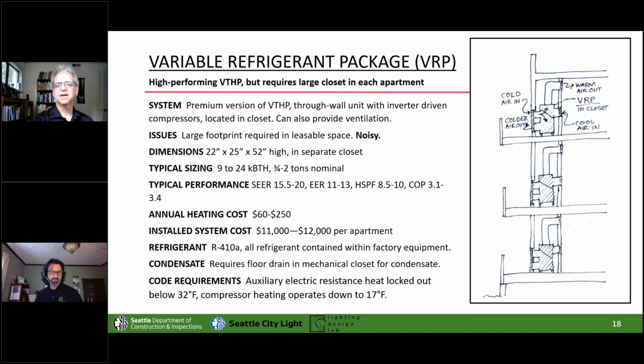A relative of this, but a little better performer, is a variable refrigerant package. Same closet in the corner at the exterior wall. And by the way, you don't have much exterior wall to work with in most modern apartments, and so this takes away some of it. But it's a little bit more expensive, and I guess it's the same noise problem. Is that right, Ben? It's a little better. So this has a variable speed compressor. That's the main difference. Only one manufacturer makes it, so it's proprietary and priced that way.